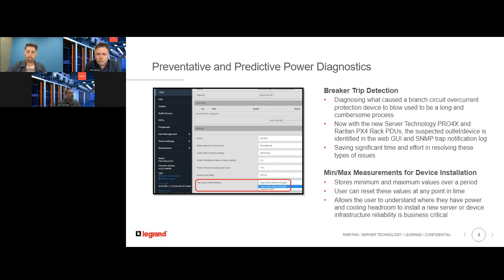So I thought I would take a couple of use case examples and go through them. One of the key ones is breaker trip detection. Any PDU that's rated 30 amps or above is required to have overcurrent protection devices or branch circuits within the device, and they're typically either fuses or breakers. When a branch circuit is tripped, in many cases, if there's not a review of the trip curves between that and the breaker upstream, whether it's an RPP or a busway system, you can even get the upstream breaker to trip, which can be very dangerous because you may lose the whole PDU.